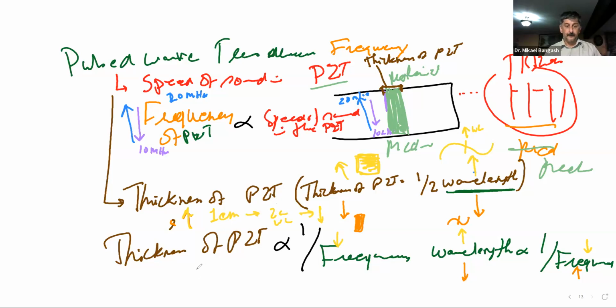a thin PZT, a PZT which had less thickness, let's say 1 millimeter thick, that's mainly going to produce a wave which has a wavelength of 2 millimeters. Compared to the yellow one up here, that is a shorter wavelength. But since wavelength and frequency are inversely proportional, that short wavelength is going to give us a high frequency transducer.